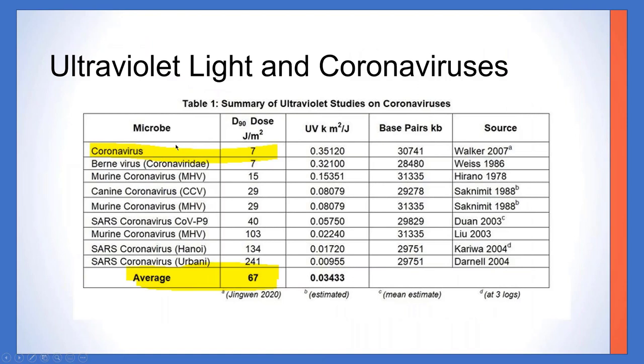If you look at the summary of all the different coronaviruses, they start out at a very small dose, but different strains have different kill rates, with an average of about 67 joules per meter squared to get a 90% kill rate. We typically, when working with clients, would rather pick the hardest one—the one that takes the most energy to kill—so that once we find out what COVID-19 will do against UVC light, which we believe will be less than this worst case, we can still give that confidence level in the system design.